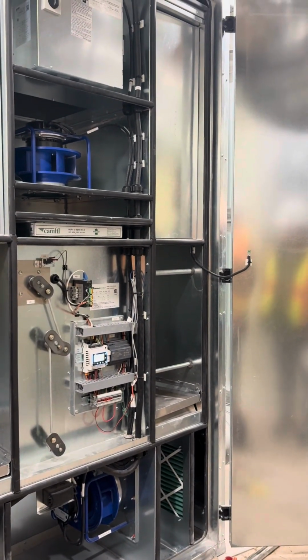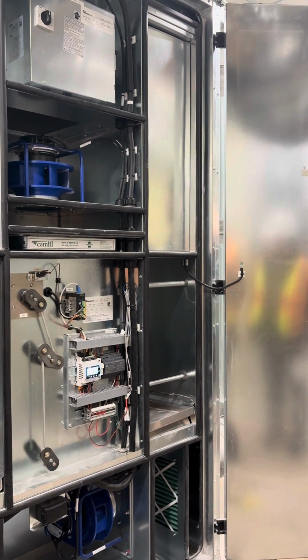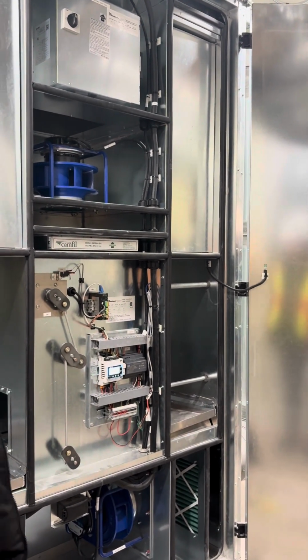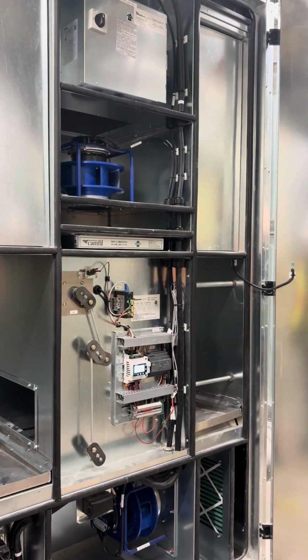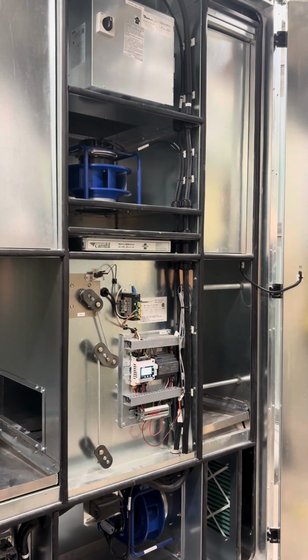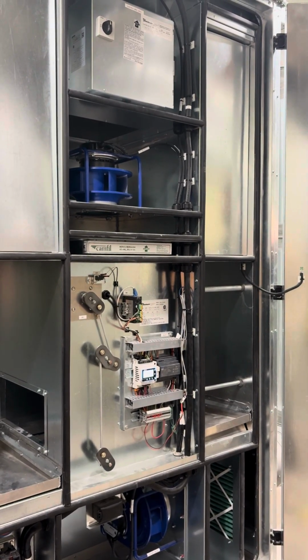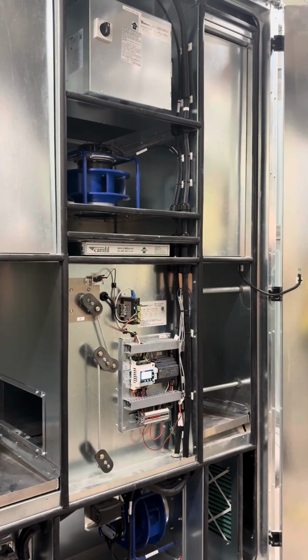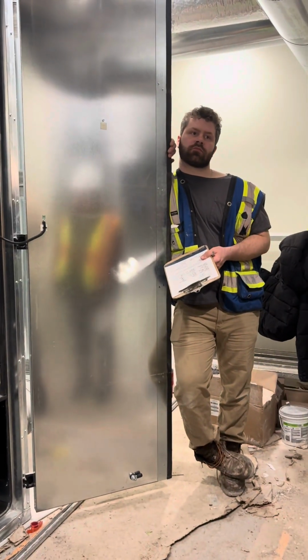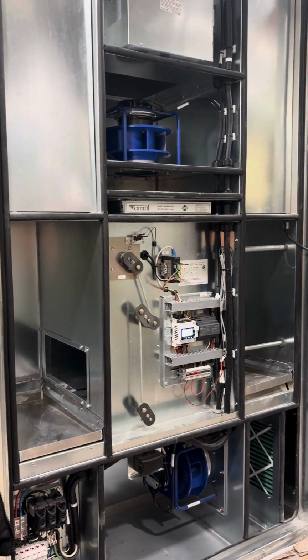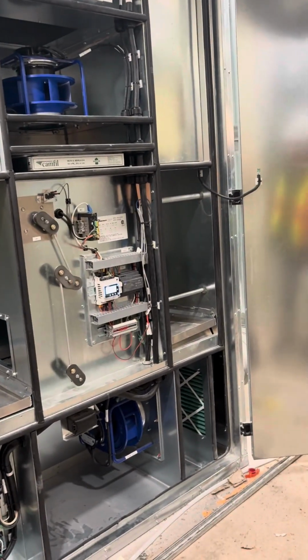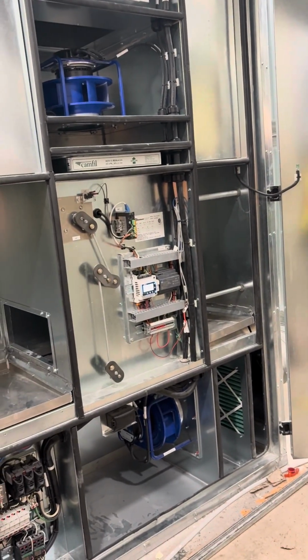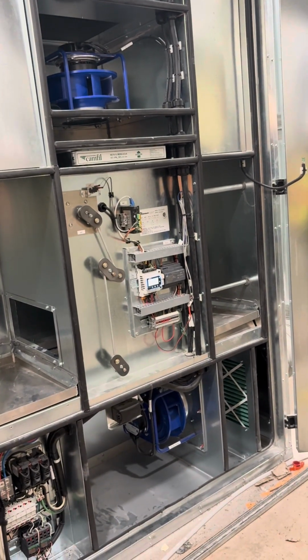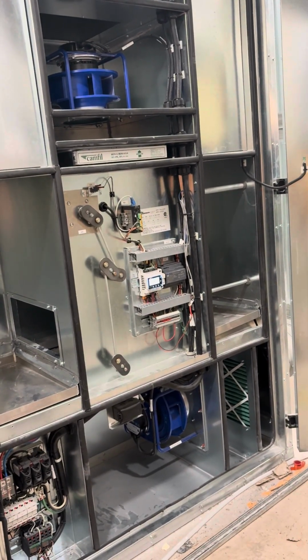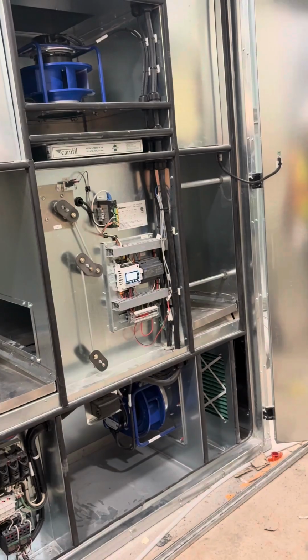So if it's hot outside, it's bringing in whatever that outside air is. It's not delivering much air to each suite, you're looking at around 30 per the balance report, but it will bring in humid air in the summertime. There's no condenser, so it won't condition it, it can get stuck that way. I'll take note of that. So hallways will complain about being really hot, but there's not much you can do. 21 is probably the set point, and you'll leave it at that for the entire year.